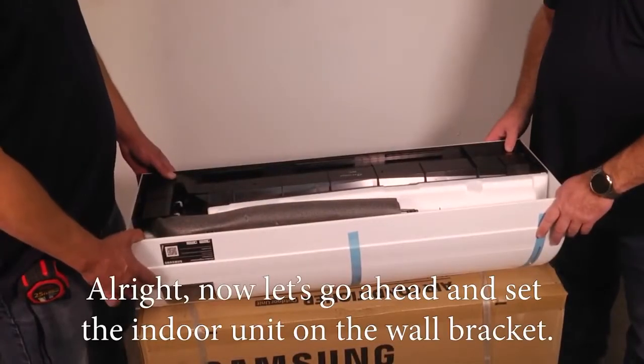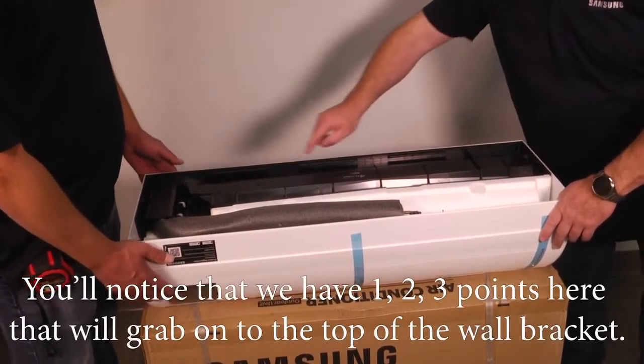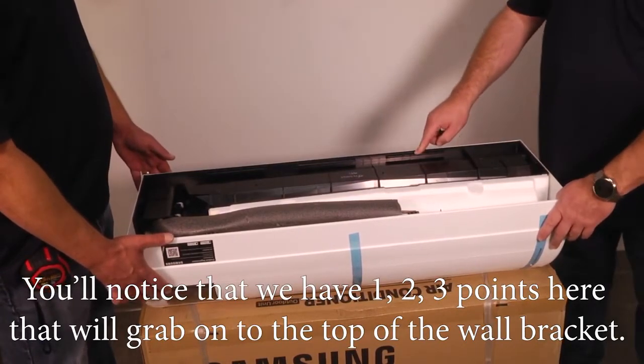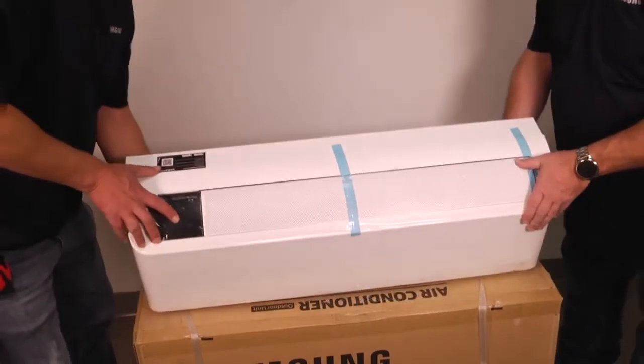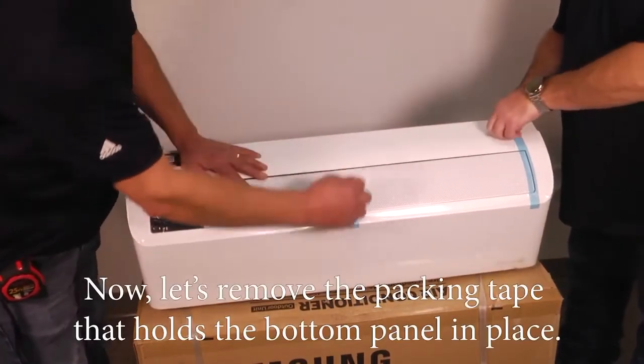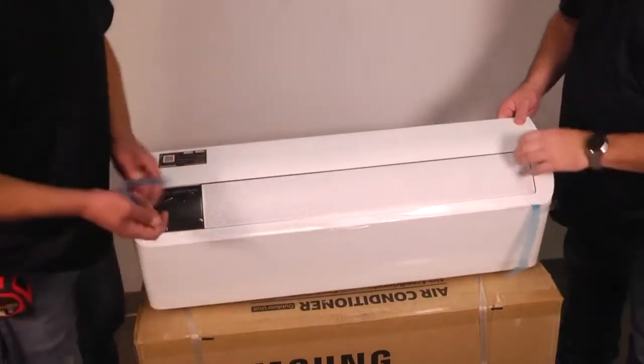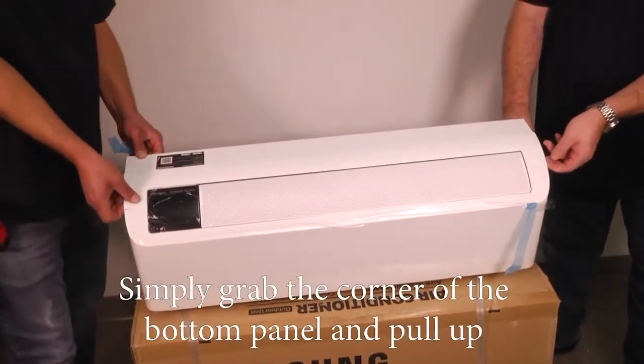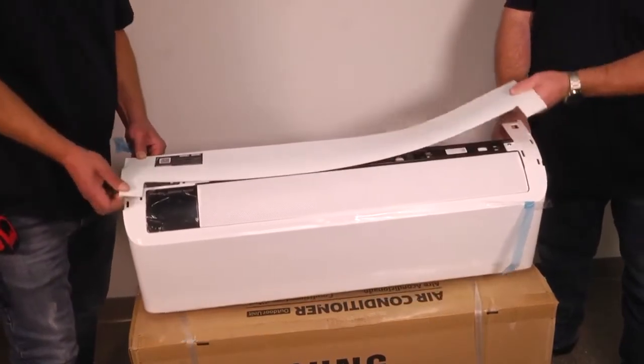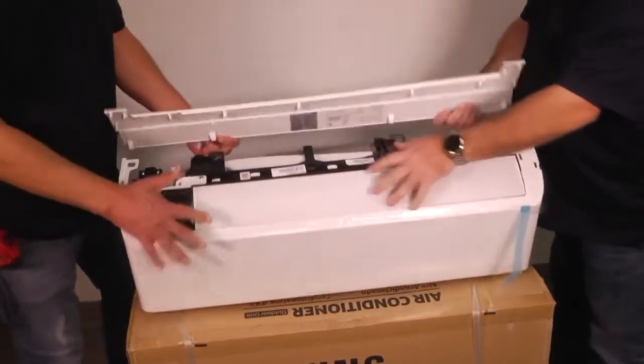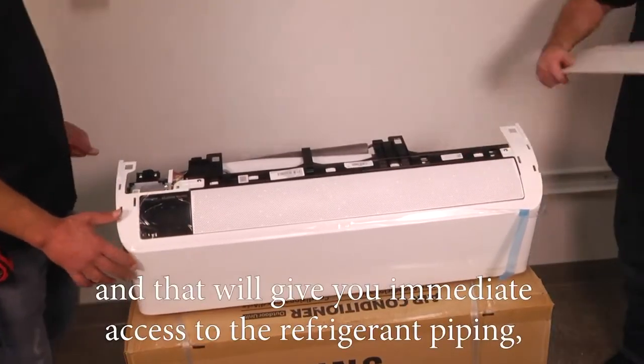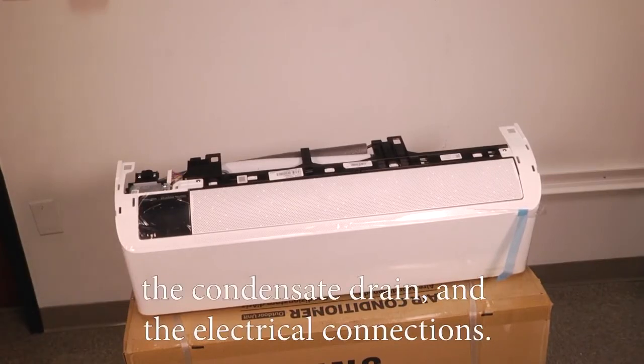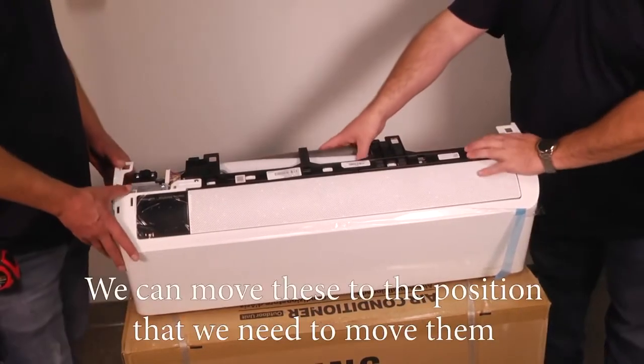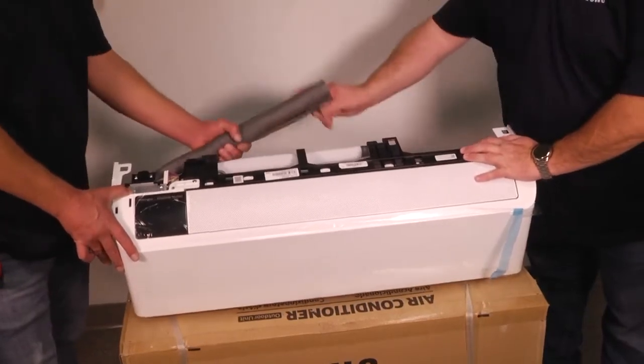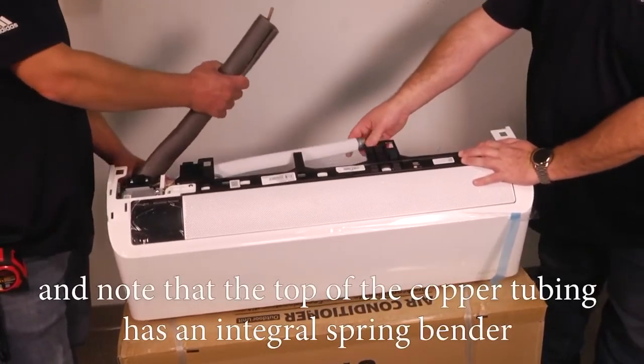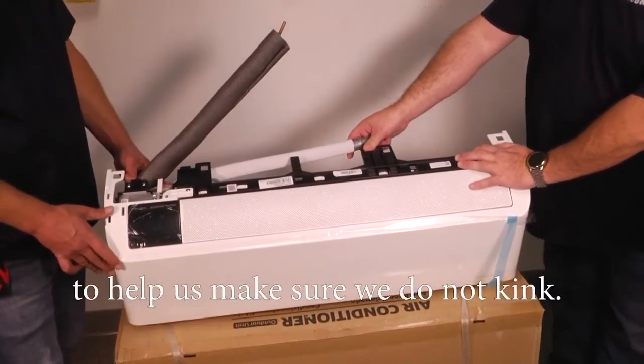All right, now let's go ahead and set the indoor unit on the wall bracket. You'll notice we have 1, 2, 3 points here that'll grab onto the top of the wall bracket. Let's rotate the unit over. Now let's remove the packing tape that holds the bottom panel in place. Simply grab the corner of the bottom panel and pull up. And that will give you immediate access to the refrigerant piping, the condensate drain, and the electrical connections. We can move these to the position we need to move them. And note that the copper tubing has an integral spring bender to help us to make sure we don't kink.